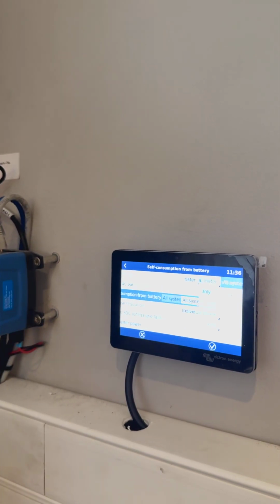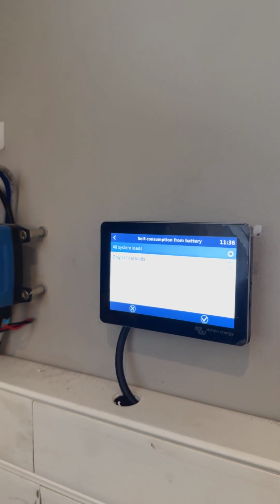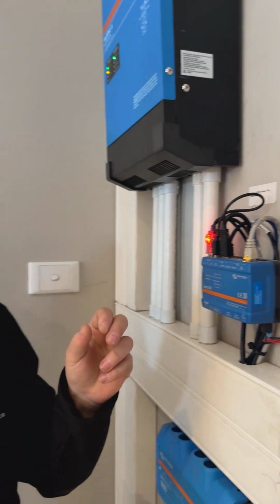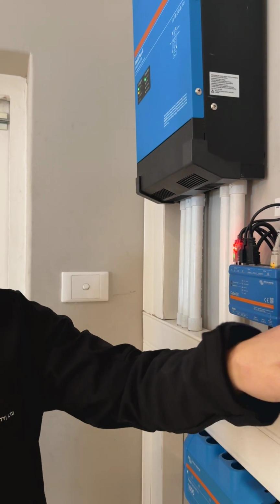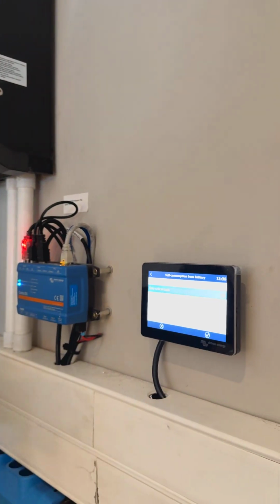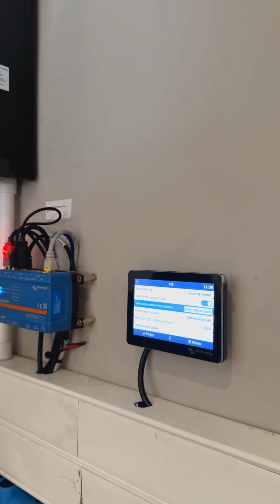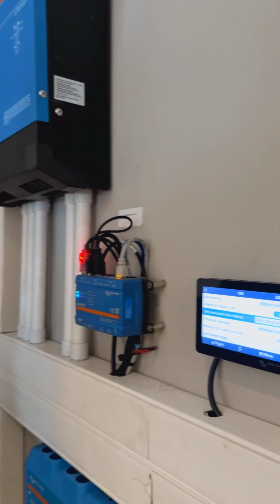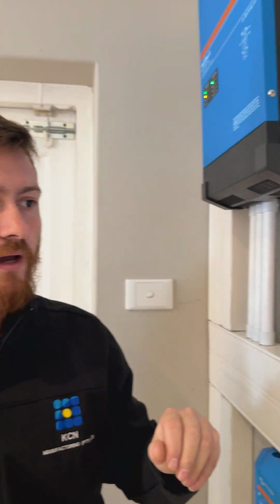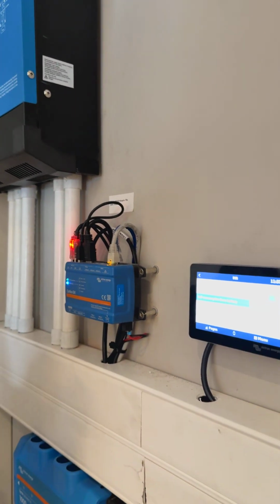Your self-consumption from battery is an extra setting that will help. If you do not want your solar to feed your non-essential loads through the energy meter, and only want to use your energy meter to measure your non-essential loads, you can set self-consumption on critical loads only. So your battery will not discharge to non-essential loads and your solar will not feed to non-essential loads - it will only go to your critical loads.